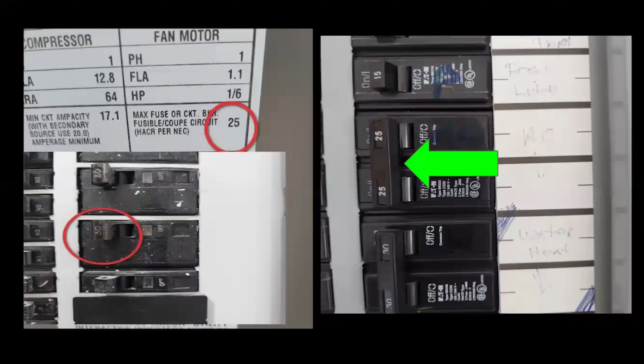If it's not, and it's more than that, that air conditioning unit might be voided because of the higher amperage. So we want it to trip at 25 amps. In other words, what can happen is what they call startup energy - when the motor turns on, all those electrons are flowing through and hitting it. Let's say the motor doesn't start up, but it keeps sucking that energy and absorbing it. At 25 amps it's going to shut off, but at 30 amps it might start a fire.